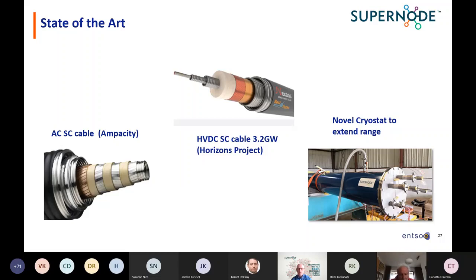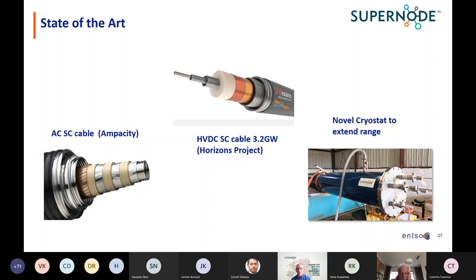Superconducting cables can handle both AC and DC technology — they love DC. As part of the EU Horizons Best Paths project, a trial was done with a superconducting DC cable where a single pole carried 10 kiloamps at 320 kV, which is 3.2 gigawatts. With a bipole you're looking at 6.4 gigawatts in a very small space — and that was actually a low-temperature superconductor.